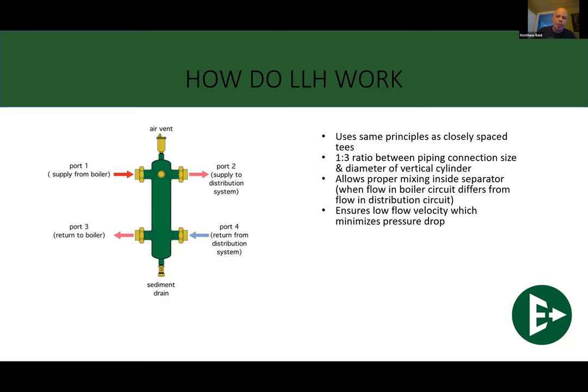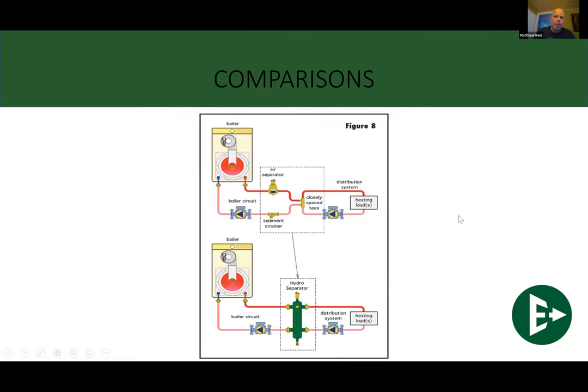It works on the exact same principles as closely spaced tees. What goes in must come out. And they're designed to be sized so that they are four pipe diameters apart from each other. These are three, because like I said, you can't make them too close. And they can do all sorts of things built into one. Here we have up on the top this air separator into a set of closely spaced tees, into what we'll call a dirt separator, and then back to the boiler.